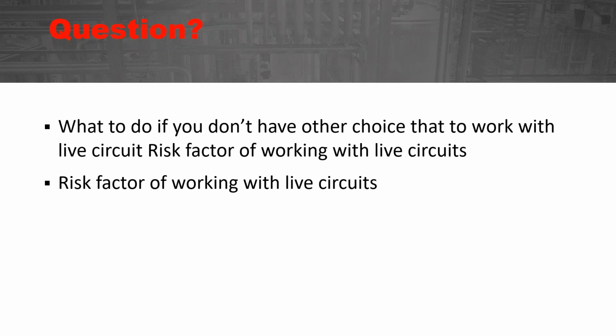So we have to be careful about doing energized work, and does it meet one of the 3 allowances in 70E? Now, let me mention, OSHA has those 3, plus they have a 4th one. The 4th one, OSHA says, if you turn off the circuit and it eliminates all the lighting in the room, then it's okay to leave the electrical on. This is not in 70E. And when OSHA ever updates their electrical safety rules, I guarantee that's going to come out.